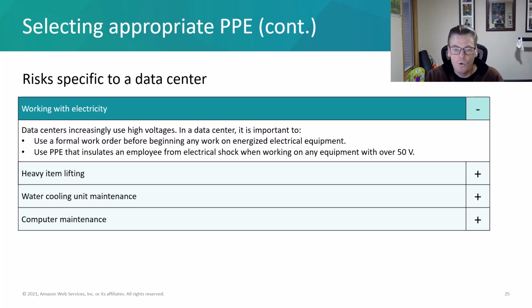From an IT standpoint, working with electricity, we aren't going to deal with a lot of the more dangerous levels of electricity. Most of the electricity we're going to be dealing with is the incoming electricity into the IT equipment. But our HVAC people, for example, are going to be dealing with a lot more. Our maintenance department people who deal with our electrical work, making sure that our generators and all of that other stuff work, are working with a lot more dangerous electricity than an IT worker. But since the data center is going to use high voltage, it's important to use a formal work order before beginning work on any electrical equipment, and use proper PPE that's going to insulate that employee from electrical shock when they're working on any equipment that's over 50 volts.